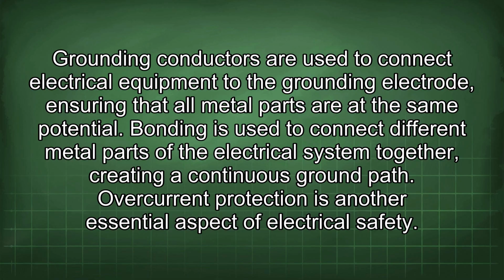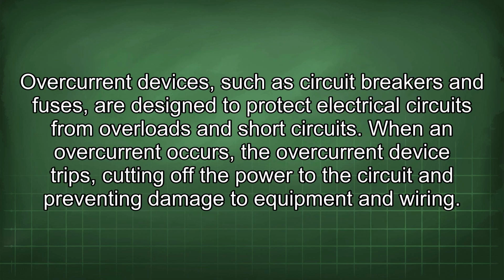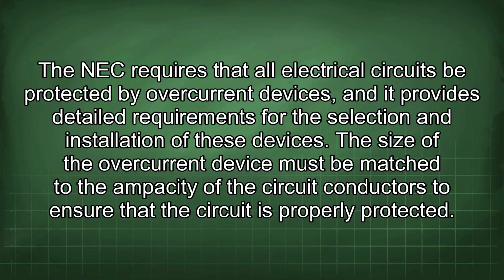Overcurrent protection is another essential aspect of electrical safety. Overcurrent devices, such as circuit breakers and fuses, are designed to protect electrical circuits from overloads and short circuits. When an overcurrent occurs, the overcurrent device trips, cutting off the power to the circuit and preventing damage to equipment and wiring. The NEC requires that all electrical circuits be protected by overcurrent devices, and it provides detailed requirements for the selection and installation of these devices. The size of the overcurrent device must be matched to the ampacity of the circuit conductors to ensure that the circuit is properly protected.